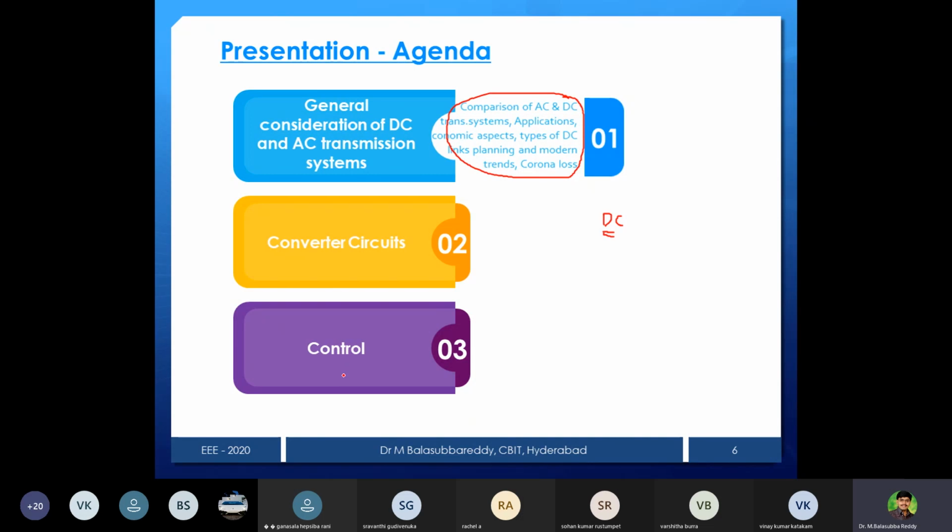They tested DC filters, AC filters, and existing plants, and from the existing plants they quoted failures in components at 7 years, 11 years, and 13 years. AC filters they quoted 12.6 years, DC filters 19.7 years, and then the smoothing reactor.